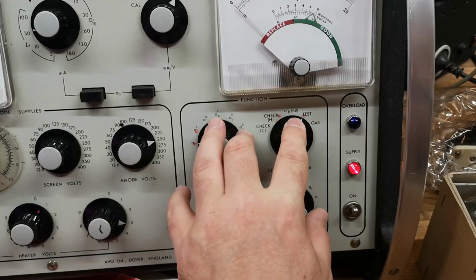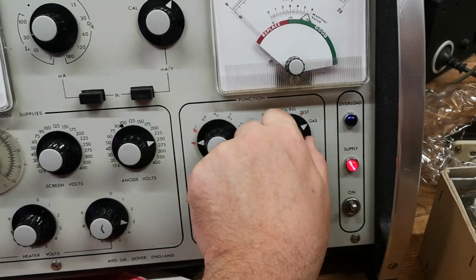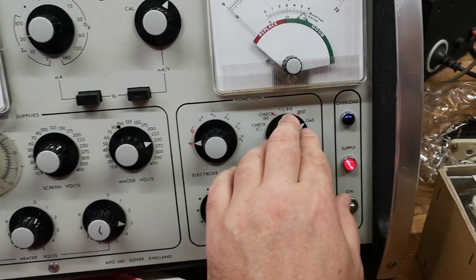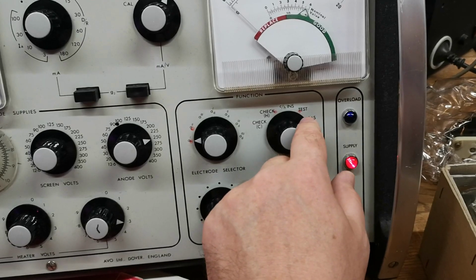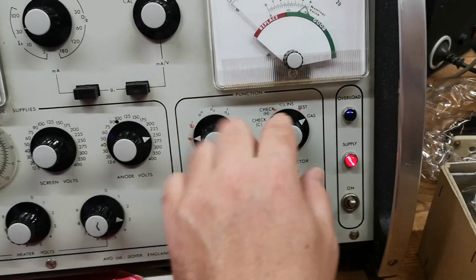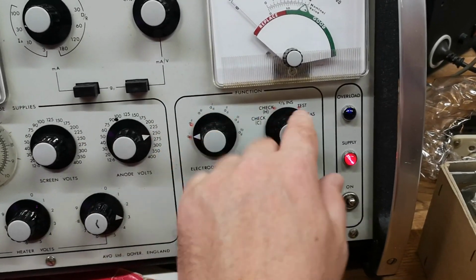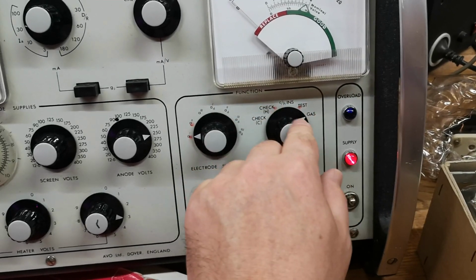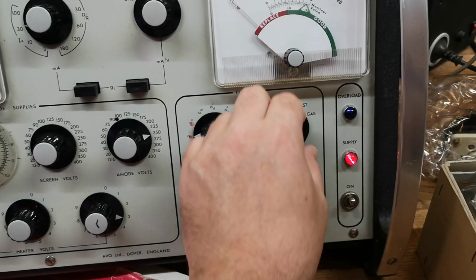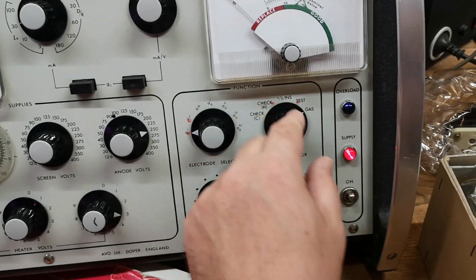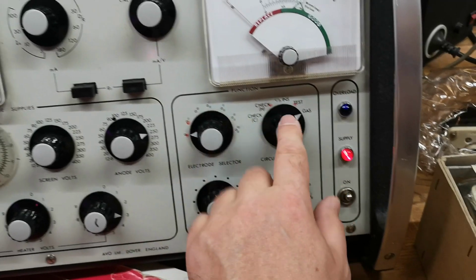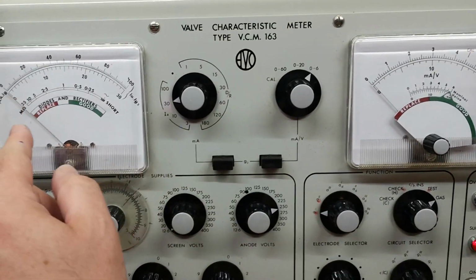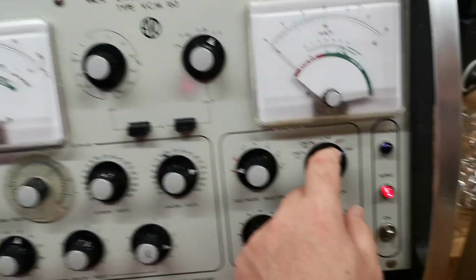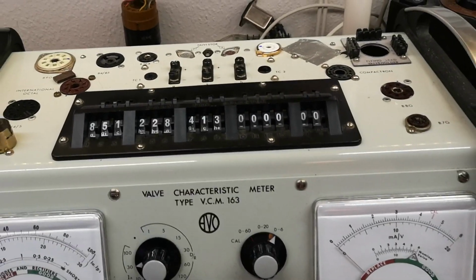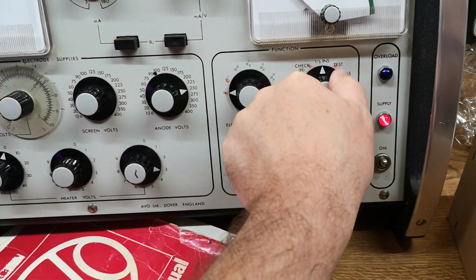So that is the main functions. It also has a gas test. I believe what it's doing here, it's actually changing the bias, and then it's measuring if there is any leakage current. That means if there is leaked gas into the tube, you could probably see a current. So in this case, you should of course see nothing on the meter, and of course we will see nothing because we didn't mount a tube.